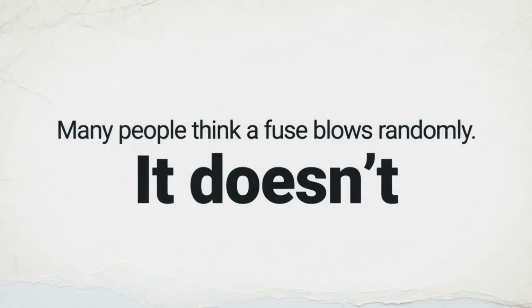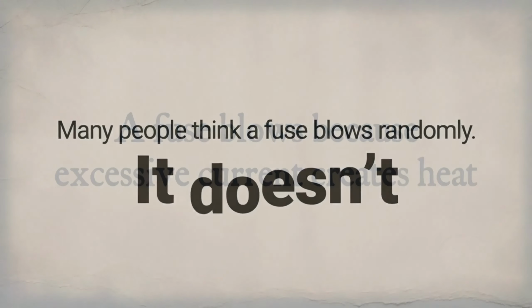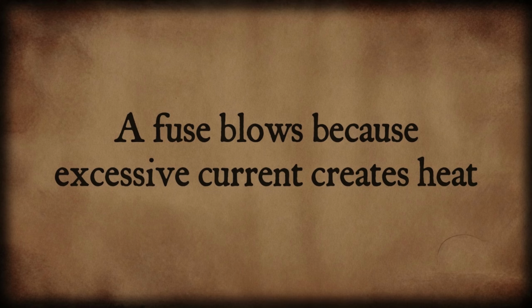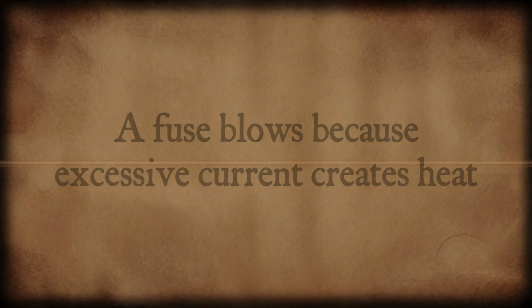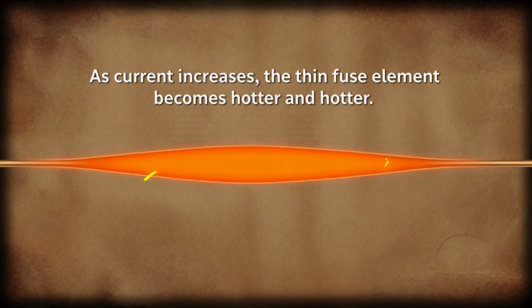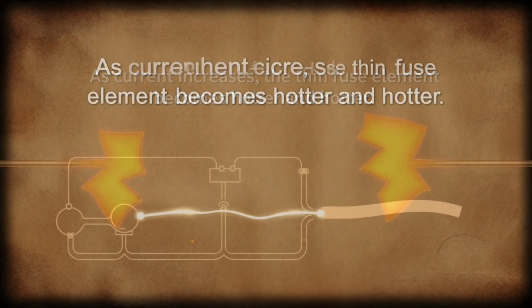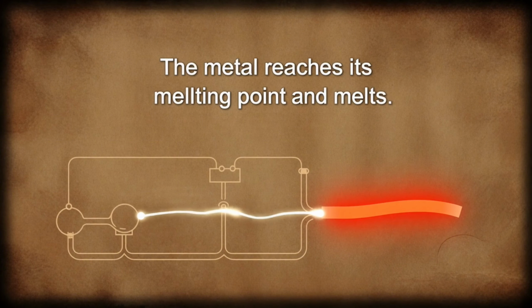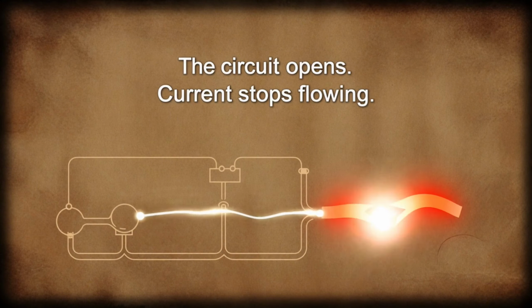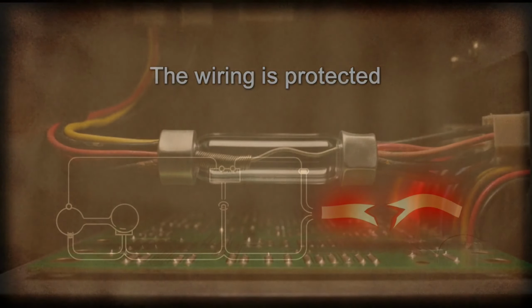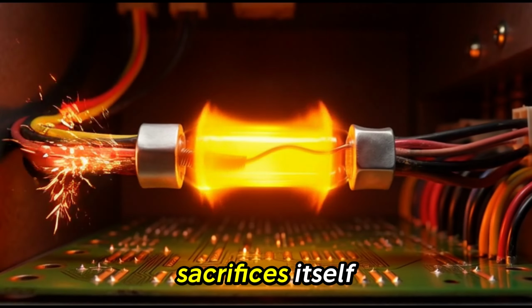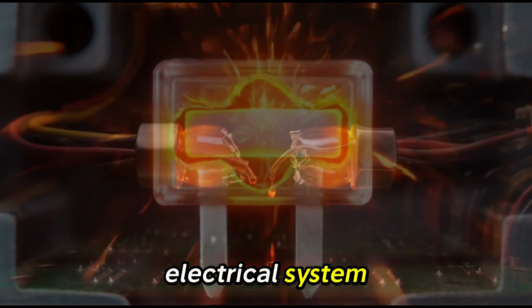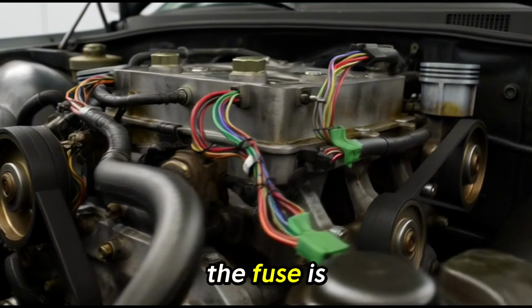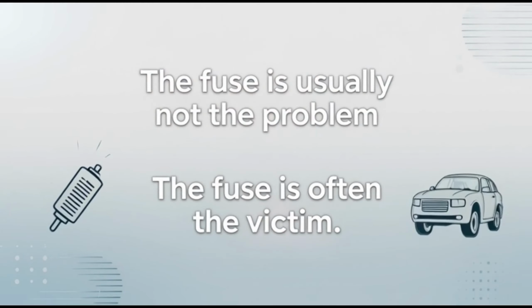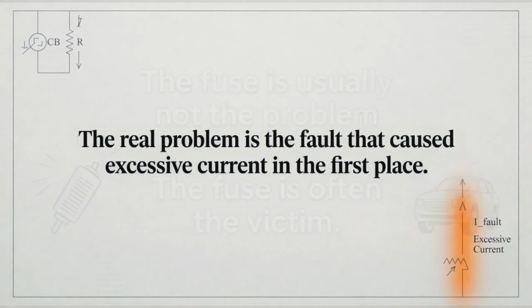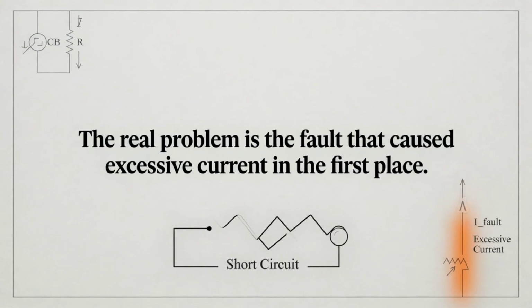Many people think a fuse blows randomly. It doesn't. A fuse blows because excessive current creates heat. As current increases, the thin fuse element becomes hotter and hotter. Eventually, the metal reaches its melting point. The element melts, the circuit opens, current stops flowing, and wiring is protected. In other words, the fuse sacrifices itself to save the rest of the electrical system. Whenever a fuse blows, remember, the fuse is usually not the problem. The fuse is often the victim. The real problem is the fault that caused excessive current in the first place.